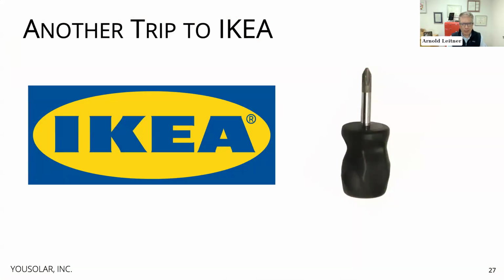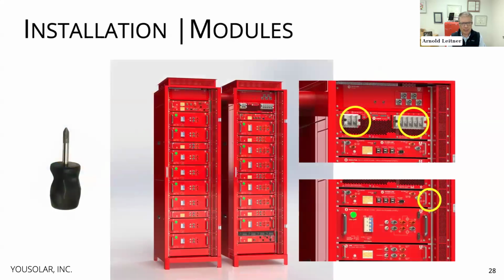We're not quite done—we haven't managed to make everything plug and play with a click-lock blade connector. So another short trip to IKEA, back to the service department, to get a hex head and a Phillips, and then proceed. We have lugs on the terminal block of the inverter, and we also have to secure the rack with standard screws to the rack rail, but those are the only two tools required. Everything else, including the interconnection between cabinets—the 350 ampere, 133 kilowatt cabinet-to-cabinet interconnection—is a click-lock connection.